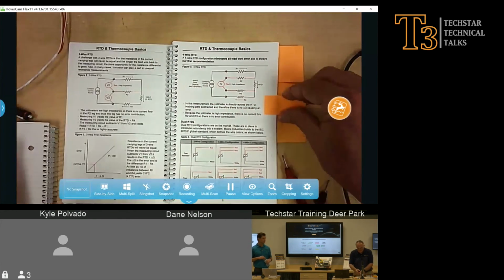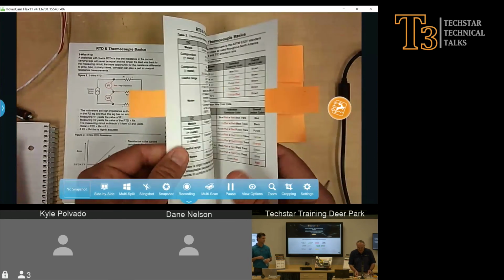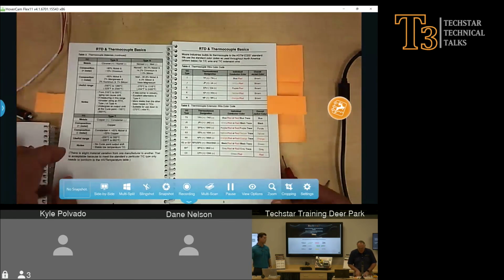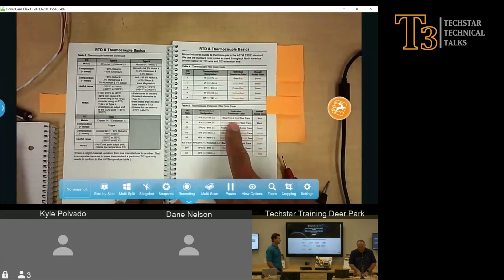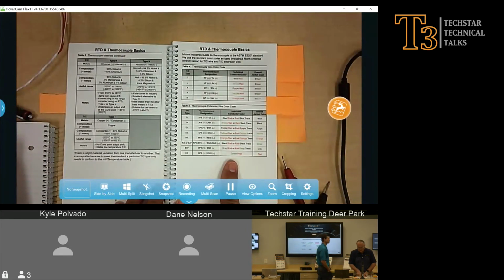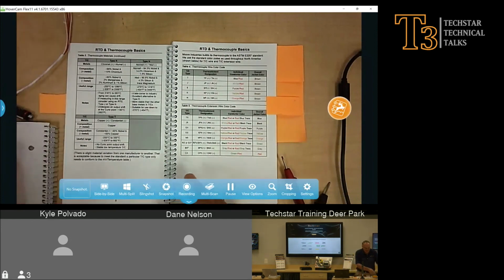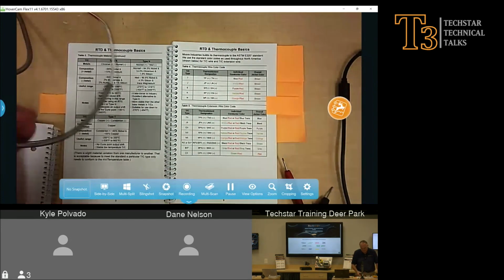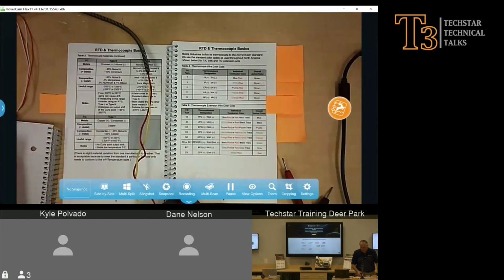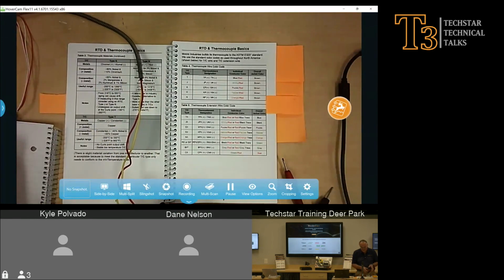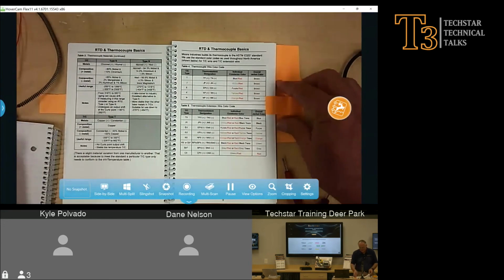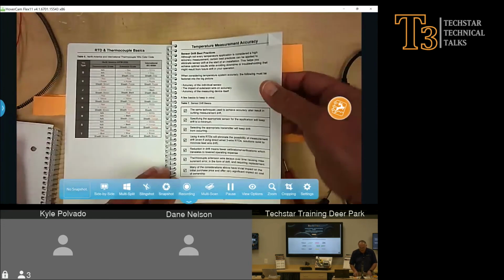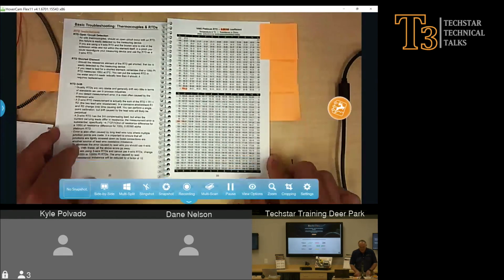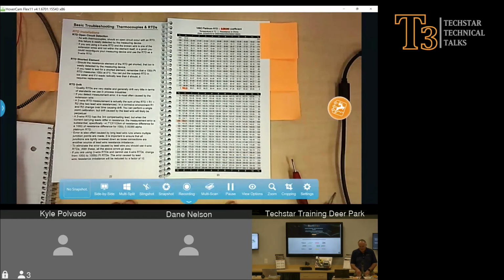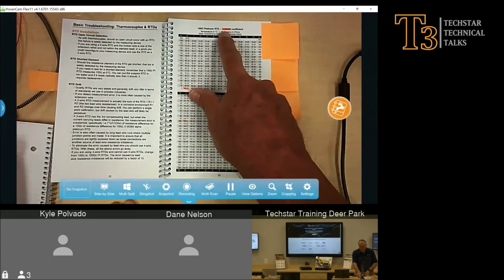And in the book, I also just wanted to go over a few things that I highlighted. Page 9, you know that thermocouples follow a color pattern. So we know that a type K thermocouple here is yellow and red. A type J thermocouple is white and red. So that's always good to have. Now, I highlighted these to talk a little bit about a platinum RTD. Here's the 100 ohm platinum, 0.00385 ohms per degree C.